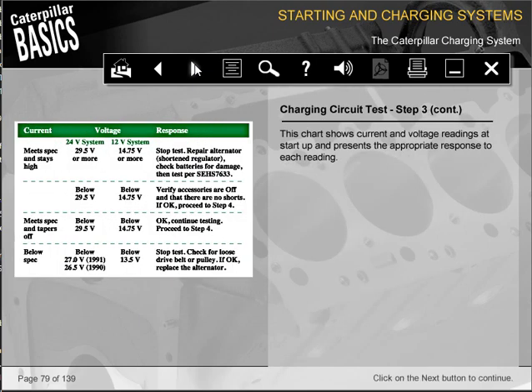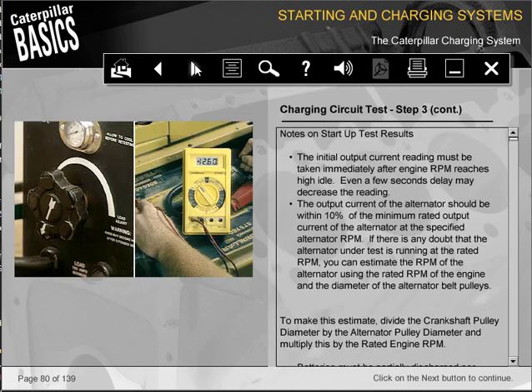This chart shows current and voltage readings at startup and presents the appropriate response to each reading. Notes on startup test results. The initial output current reading must be taken immediately after engine RPM reaches high idle. Even a few seconds delay may decrease the reading.